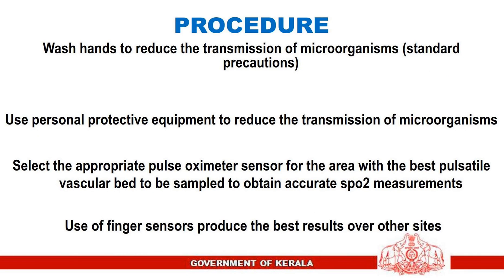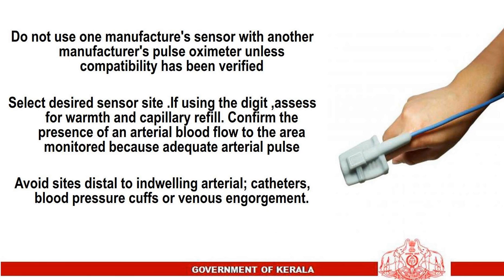Procedure: wash hands to reduce the transmission of microorganisms as standard precautions. Use personal protective equipment to reduce the transmission of microorganisms. Select the appropriate pulse oximeter sensor for the area with the best pulsatile vascular bed to obtain accurate SpO2 measurements — use of finger sensors produces the best results. Do not use one manufacturer's sensor with another manufacturer's pulse oximeter unless compatibility has been verified.